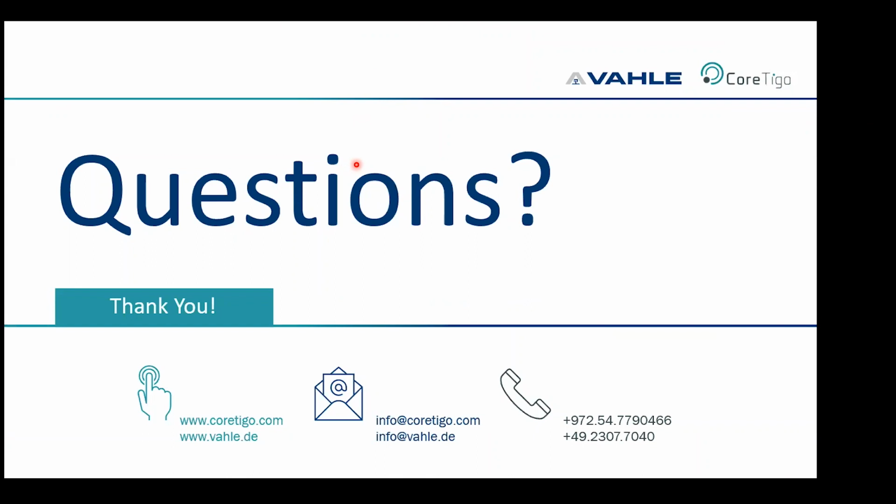First question is, when you're saying 1 million times better than every other radio technology, in which parameter are you measuring it for VAHLE Wireless? Okay, so good question. There's a concept called packet error rate. Packet error rate is how many packets failed over a large number of packets. And the standard packet error rate for Wi-Fi or for Bluetooth is around 10 to the minus 3. And with CoreTigo, with VAHLE Wireless, it's 10 to the minus 9, which means it's literally 1 million times better than these other protocols. And it's pretty much the same as the packet error rate that you get on an actual cable.